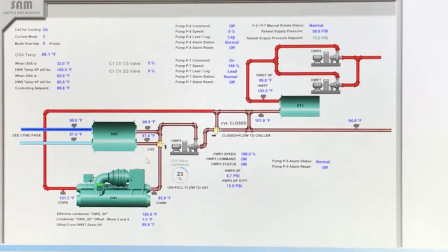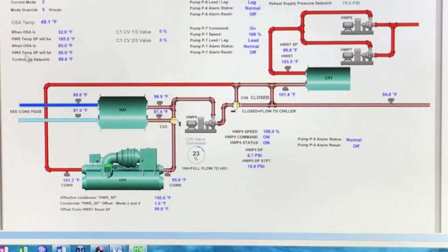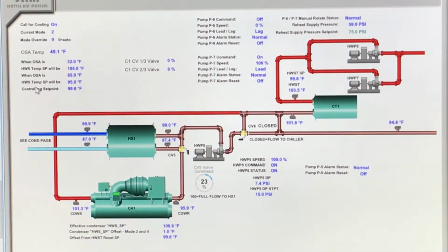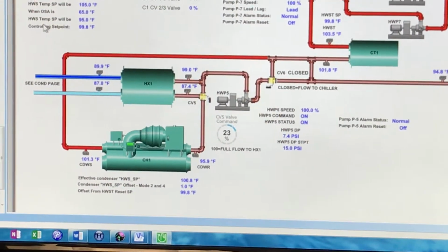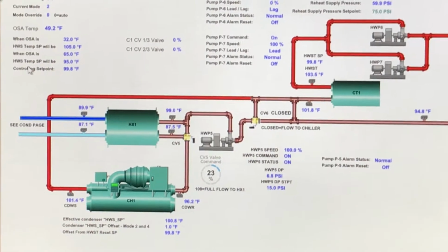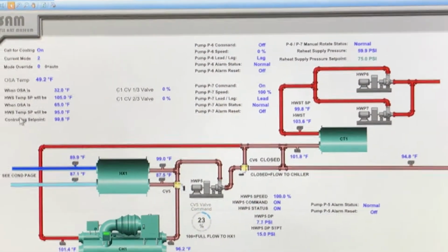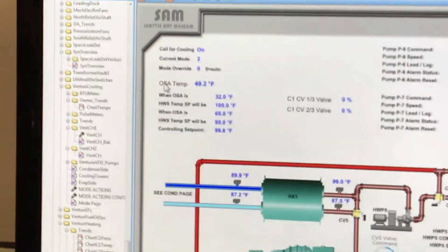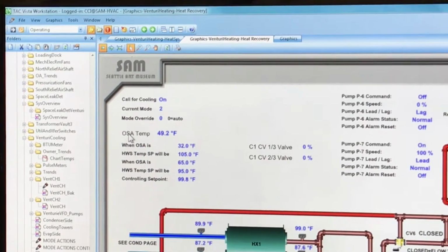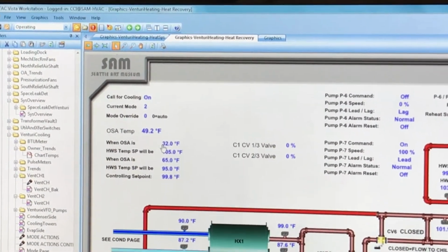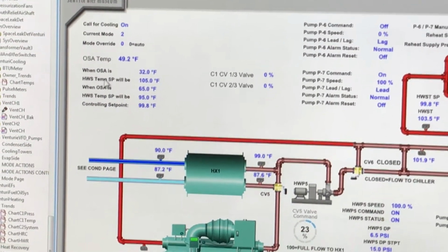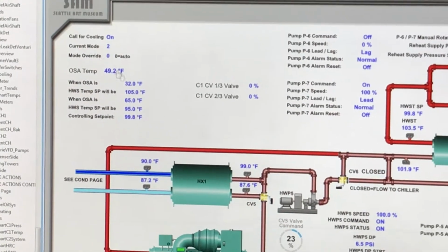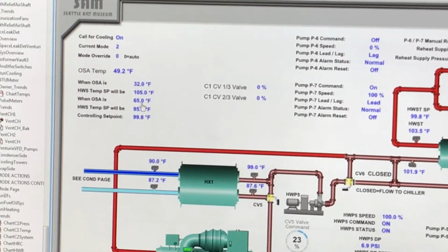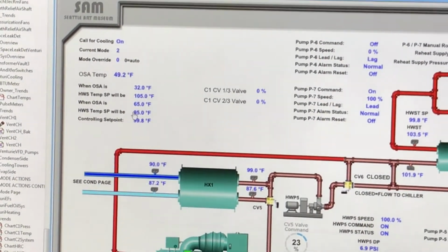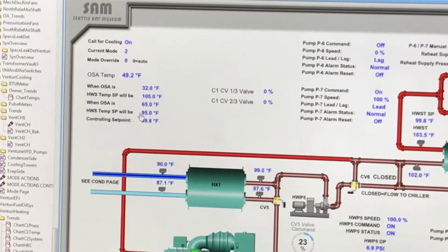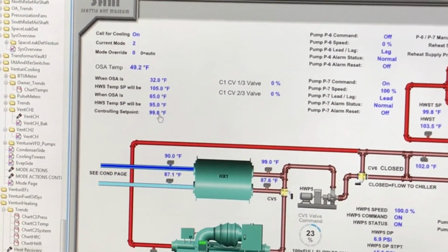Now right here we have a reset that we put in based on outside air temperature. Are you familiar with reset set points? Anybody? Okay, I'll go over it. It's not too difficult. So we're looking at outside air temperature, 49, correct? And when outside air temperature lowers to 32 degrees, the hot water supply set point will be 105 degrees. When the outside air temperature rises to 65 degrees, the hot water set point will be 95. So it lowers it, trying to save you some energy this way. The controlling set point right now is 99.8.